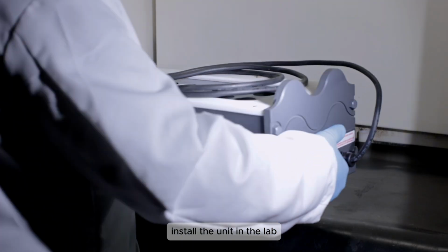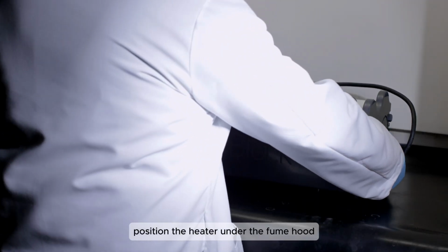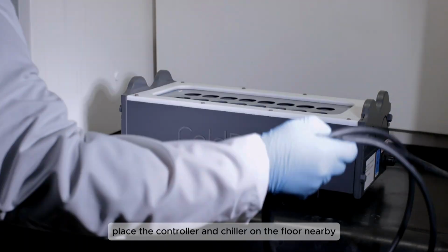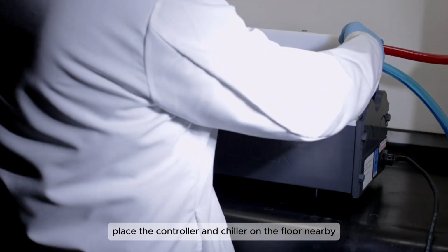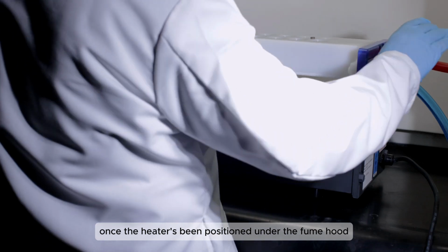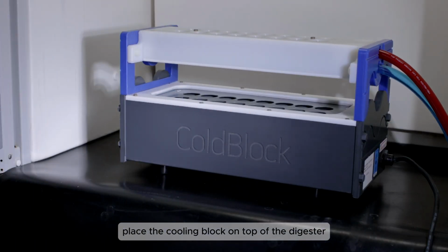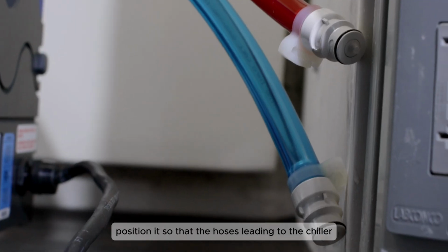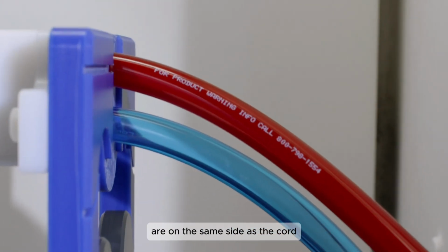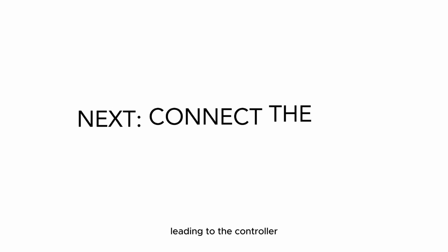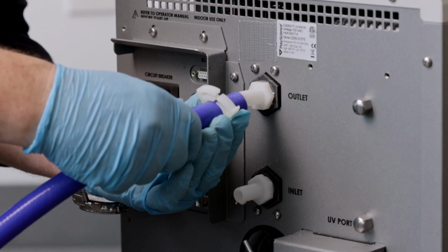Install the unit in the lab. Position the heater under the fume hood. Place the controller and chiller on the floor nearby. Once the heater's been positioned under the fume hood, place the cooling block on top of the digester. Position it so that the hoses leading to the chiller are on the same side as the cord leading to the controller.